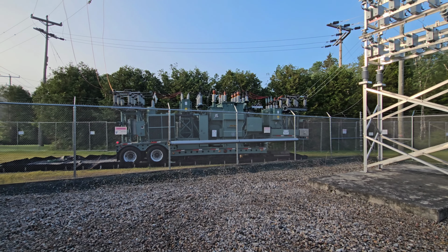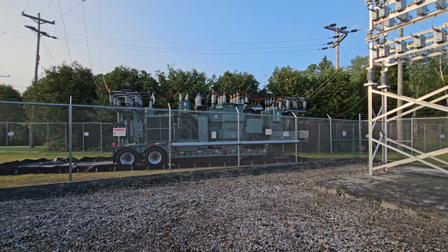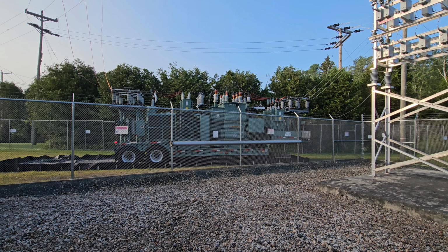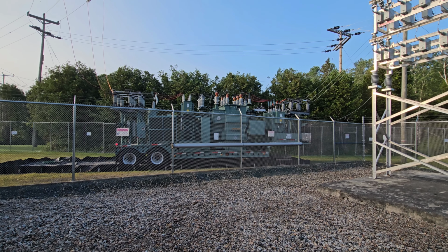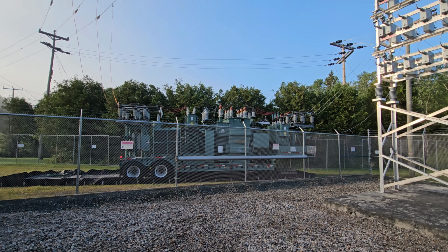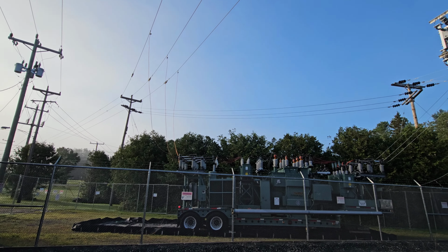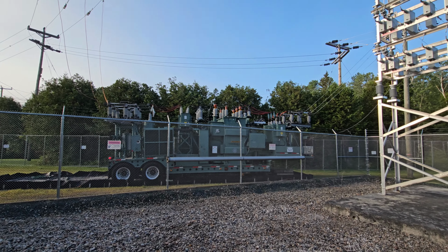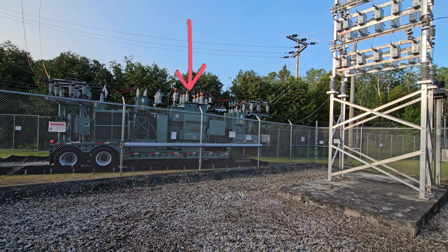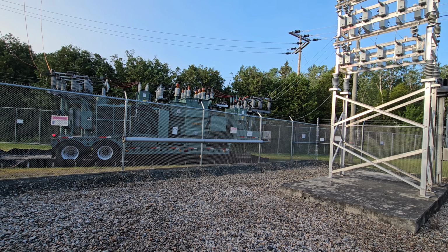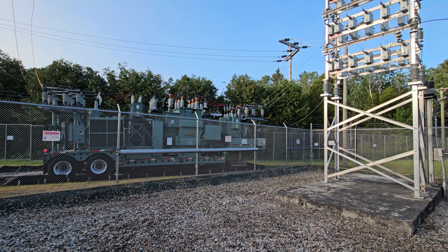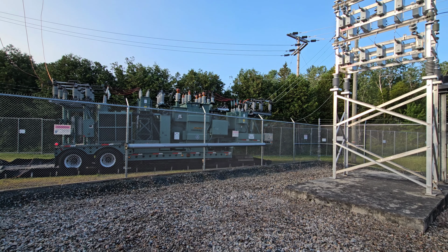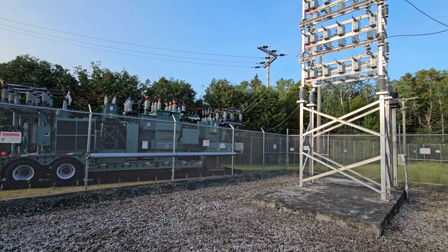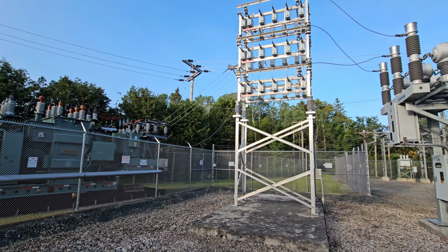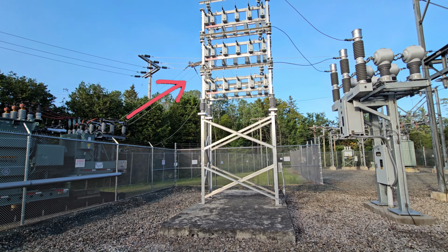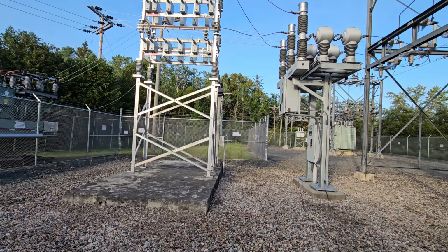Alright, so this is a mobile substation. This is brought into a yard in order to run power through while the normal substation equipment is maintained. So it's tapped up on what we call the high side. It transforms the voltage to a lower voltage. It's protected by breakers on either side. It has basically all the elements of a substation packed onto a trailer that can be hauled around, and then out this low end the power goes out to the circuits where people use it.